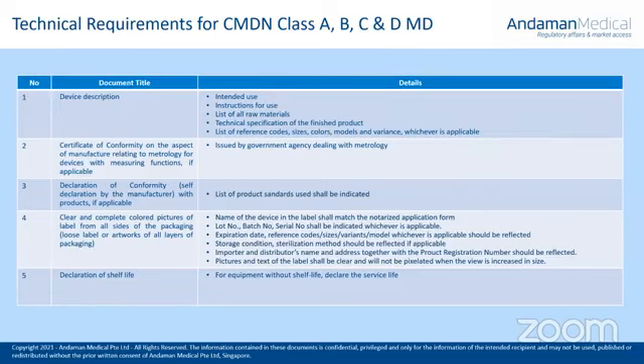So in the AMDD document, there is actually a template of the declaration of conformity. So if your manufacturer doesn't know how to do the declaration of conformity, then you can provide the template coming from the AMDD. The most important point here is to make sure that the product standards used in the device are listed, because that's the one being checked by the FDA evaluator. If you only provide the declaration of conformity without the list of product standards, then you are sure that it would be a non-compliance on your part when FDA provides you the NOD.